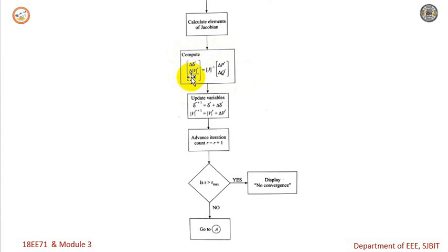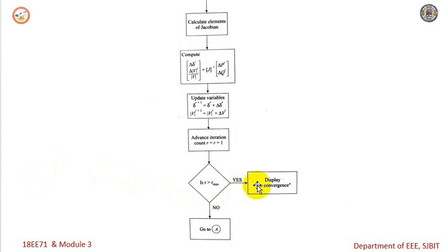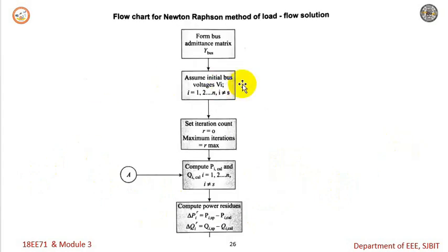Once we compute delta-delta and delta V, we update these variables for the (r+1)-th iteration: delta(r+1) equals delta(r) plus delta-delta, and V(r+1) equals V(r) plus delta V. We then advance the iteration count r to r plus 1 and check whether r is greater than r_max. If no, we go back to computing P_i and Q_i calculated and follow the same procedure. If yes, we display 'no convergence.' This completes the flowchart of the Newton-Raphson method in polar coordinates.